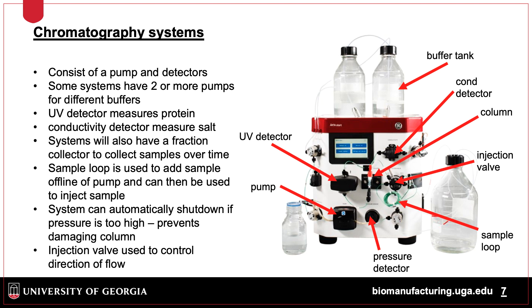A sample loop is critical for injecting sample onto the chromatography resin. Systems also have monitors that will cause an alarm if, for instance, there is too much pressure, and can automatically turn off the system to prevent damage.